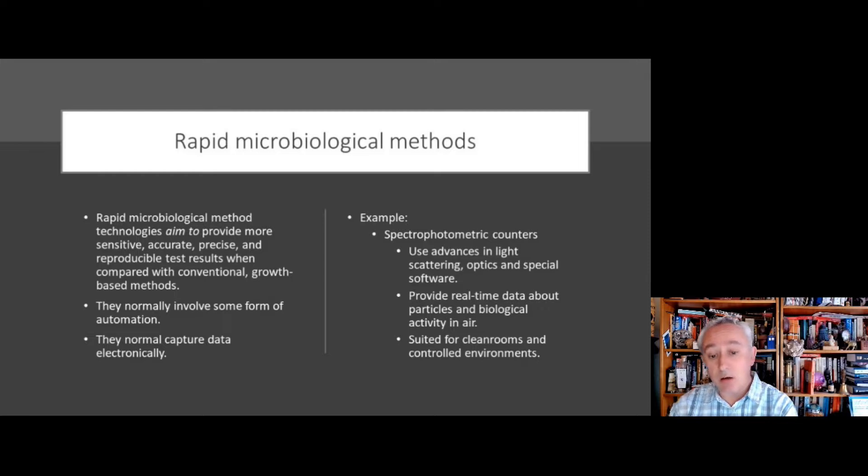These are basically extensions of the standard particle counter concept and they work on advances in light scattering techniques and through the use of special software. They provide real-time data about particles' biological activity within the air. So essentially they're differentiating between inert particles and those particles that are biologically active, and by biologically active they might be microbial.